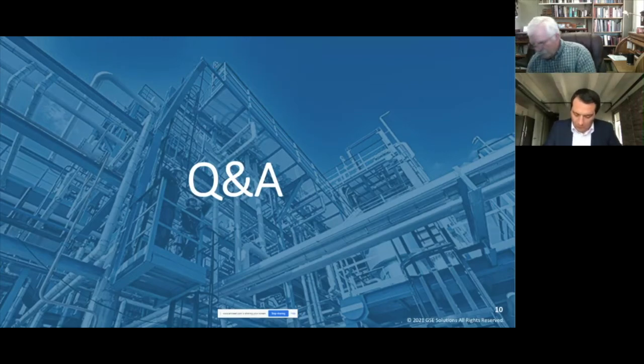But that said, the model has so much redundancy in it that unless you hit it with a hammer and really force it in a particular direction, the pull to the actual solution is usually quite strong. You really have to force some of the variables quite significantly, depending on their criticality, as Frank said. It's not every other variable that is going to cause your model to wander into the unknown. So usually you would have to be pretty drastic, or touch some very specific things that you shouldn't be touching. And one of the things we look at, as Frank said, is to make sure that a particular variable is not too dependent on any individual assumption or on any individual sensor.